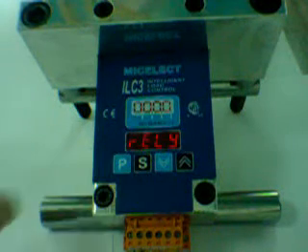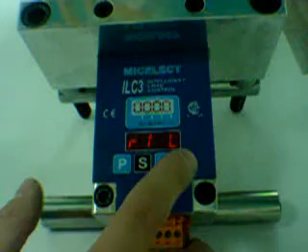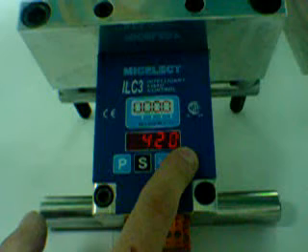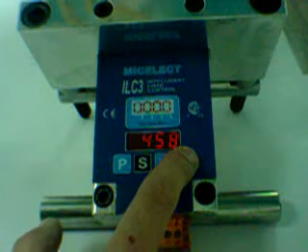You enter the relay menu, relay number 1, by high or by low, open contact or close contact, and the weight at which you want alarm number 1 to trigger.